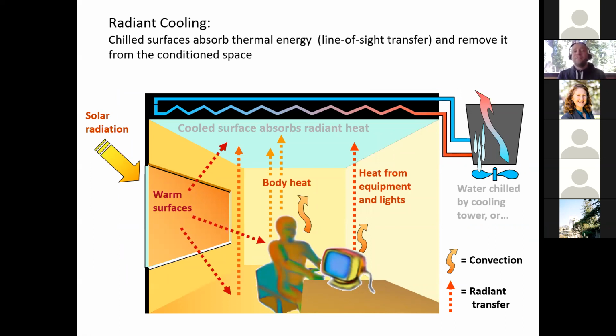I love radiant cooling. It's exceptionally comfortable without the drafts that are typically associated with all air systems. And when you have cool surfaces around you, you can actually tolerate warmer temperatures because the mean radiant temperature of the total space, the operative temperature, is still within the comfort range, even if the air temperature is a little bit warmer. And you can think about that relationship when you're sitting at the beach on a relatively cool day with cool breezes coming off of the coast, but you're very warm sitting in the sun, like you're getting all that radiation from the sun. So that's the mean radiant temperature overcoming a lower air temp. Well, the same phenomenon can work in reverse with the space being a little bit warm, but cool surfaces all around you can give you the sense of coming into a much cooler space.